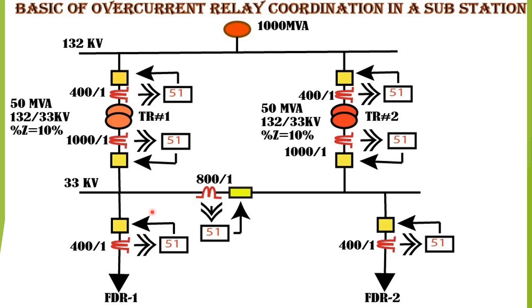In this lecture, I will discuss the basics of overcurrent relay coordination in a particular substation. The single line diagram shown is for a 132 by 33 kV substation. This substation has two 50 MVA, 132 by 33 kV transformers, each with a percentage impedance of 10%. On the 33 kV bus, two feeders are considered for ease of understanding, and there is one bus coupler breaker with the two feeders connected on each side of it.